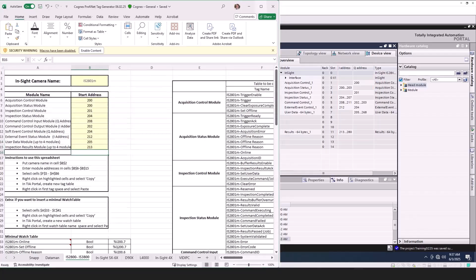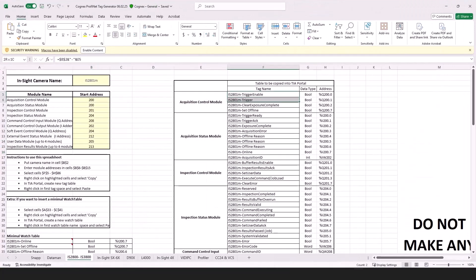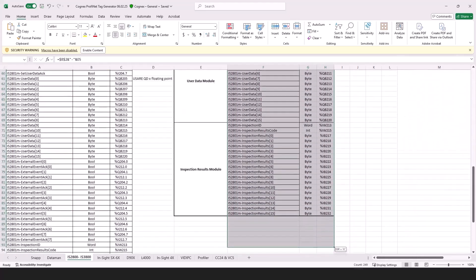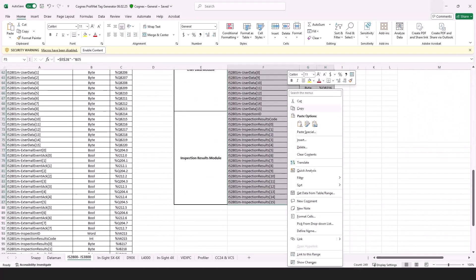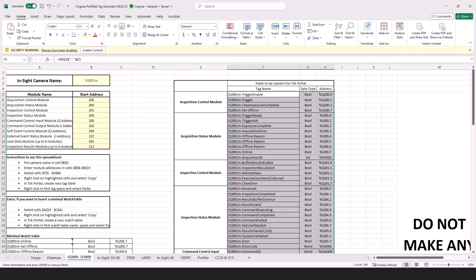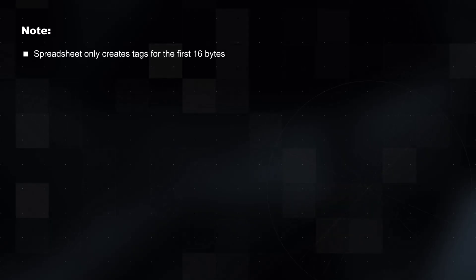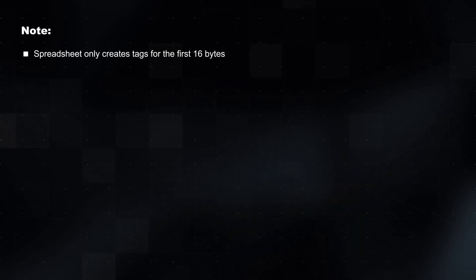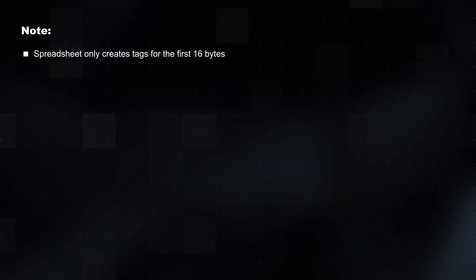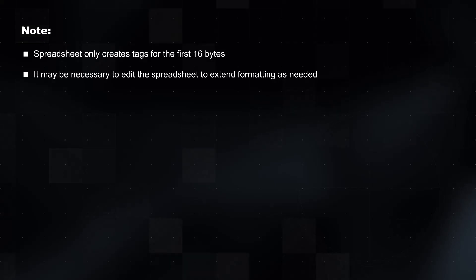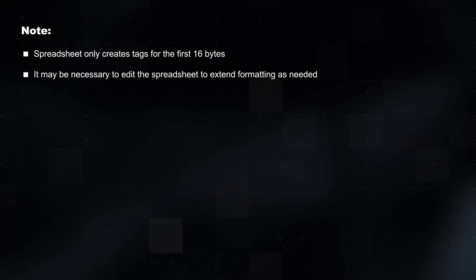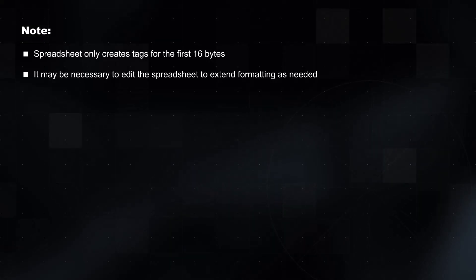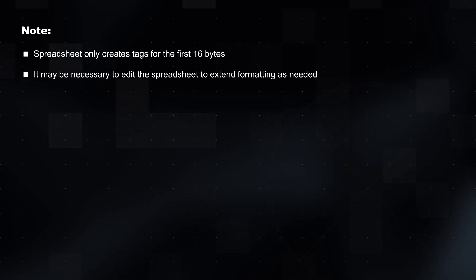Once all fields have been filled out, copy cells F5 through H87 in the spreadsheet. Right-click on the highlighted cells and select Copy. This includes all the information within the Tag Name, Data Type, and Address fields. It is important to note that the spreadsheet only creates tags for the first 16 bytes. When the size is larger than this, it may be necessary to edit the spreadsheet to extend the formatting as needed.